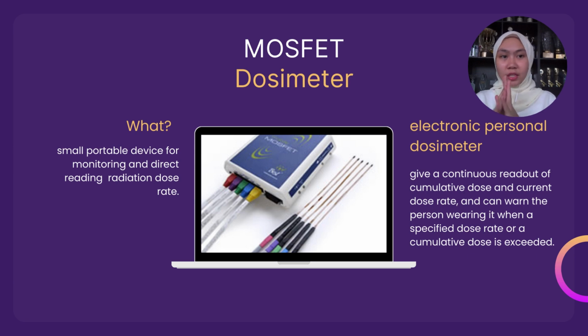We have understood MOSFET in general, so now we will learn about the application of MOSFET in the dosimeter. What is a dosimeter? A dosimeter is a small portable device for monitoring and directly reading radiation dose rate. One example of a MOSFET dosimeter is the electronic personal dosimeter. It gives a continuous readout of cumulative dose and current dose rate, and it can warn the person wearing it when a specified dose rate or cumulative dose is exceeded.